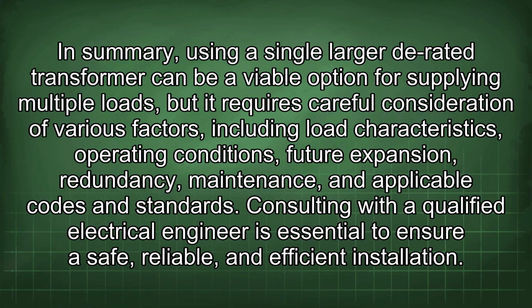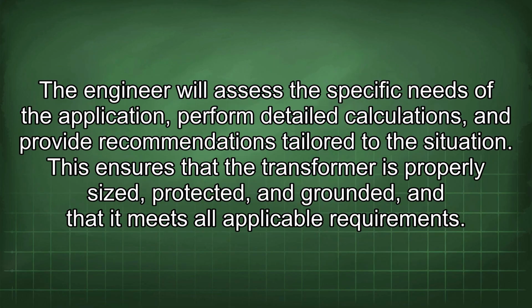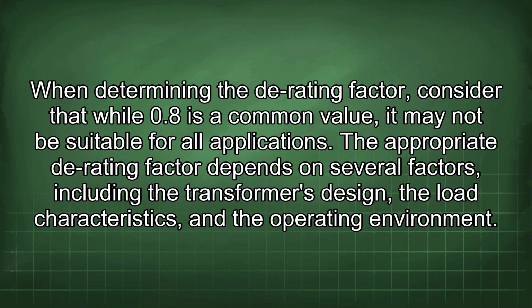Consulting with a qualified electrical engineer is essential to ensure safe, reliable, and efficient installation. The engineer will assess the specific needs of the application, perform detailed calculations, and provide recommendations tailored to the situation. This ensures that the transformer is properly sized, protected, and grounded, and that it meets all applicable requirements. When determining the derating factor, consider that while 0.8 is a common value, it may not be suitable for all applications. The appropriate derating factor depends on several factors, including the transformer's design, the load characteristics, and the operating environment.